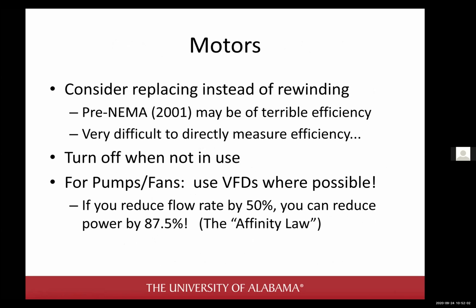Then if you buy a new motor, NEMA, I forget what the acronym is, anyway, NEMA is the premium efficiency rating for motors. And if you buy a new motor, there has to be a minimum efficiency. If you have a 20 horsepower motor, you're going to get 92% efficiency. I'm ballparking here, I don't know the exact value. I have measured directly efficiency of motors in the 70-80% range, and that is terrible for a motor.